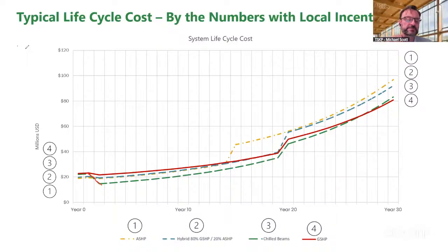I'll jump in on this one. A lot of it depends on what the soils are like, which we'll start to confirm with the geotechnical investigation at the end of this month. But we're looking probably in the range of 100 to 120 wells, about 500 feet deep. Those would be closed pipe systems, so we're not depositing any water into the aquifer—we're just looping our building or well field water through the earth to absorb or reject heat.